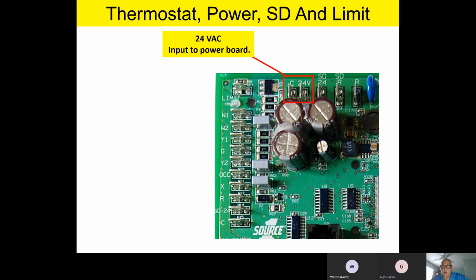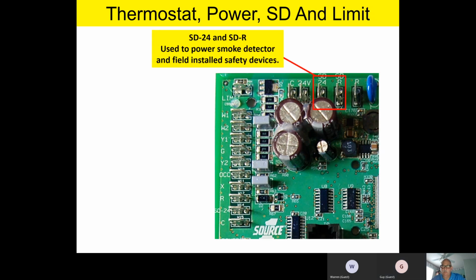Thank you. Okay, fellas, and then right there, right next to that is your SD24 and SDR used to power up your smoke detector and field installed safety circuits. And again, one more time, if you'll just make a note of this, they have to be dry relay click switch type of contacts. You don't want to use an electronic switching device or anything like that. Just use any alarm contacts, any aftermarket alarm contacts. You can put a fireman key in there. You can put whatever you want in there.